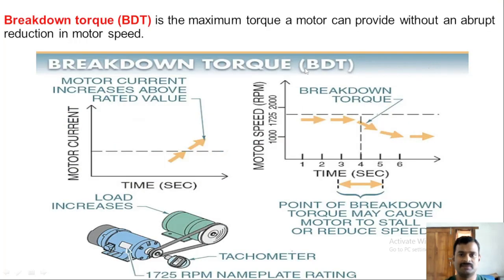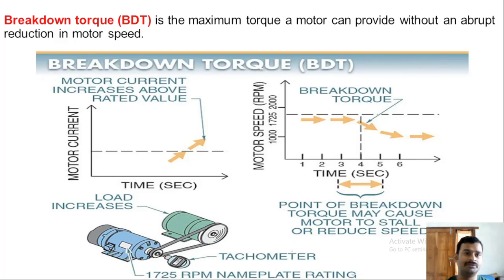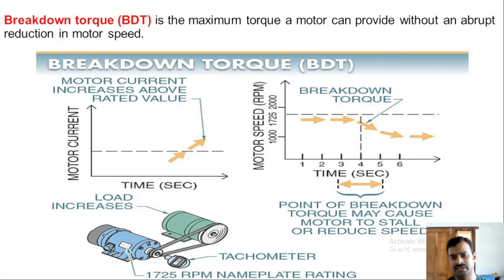Breakdown torque is the maximum torque a motor can provide without an abrupt reduction in speed. Every motor has a capacity limit for pulling load. If the load keeps increasing beyond a certain point, the motor speed starts to drop — the torque at that point is called breakdown torque. Loading beyond this limit causes the motor to approach standstill, which is a dangerous condition where coil temperatures rise and insulation may fail due to overheating.